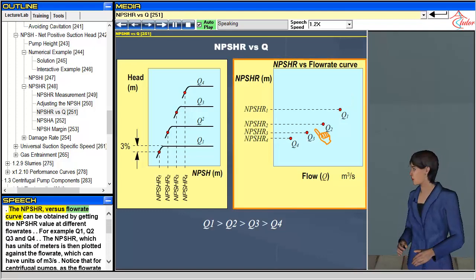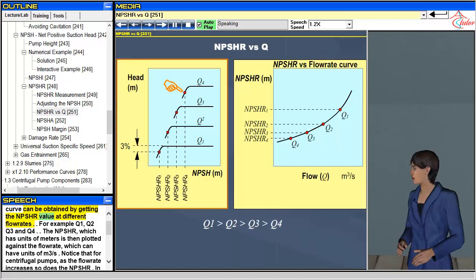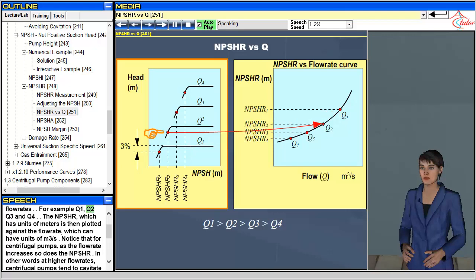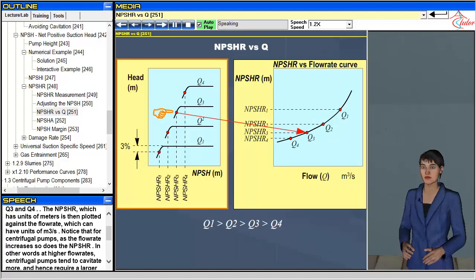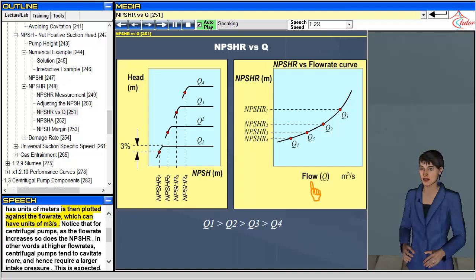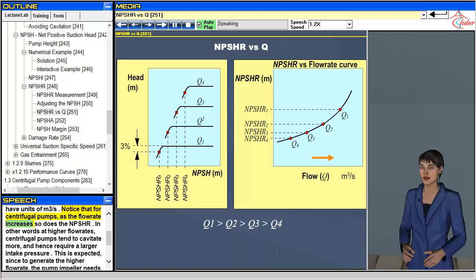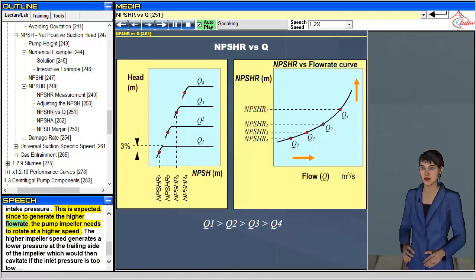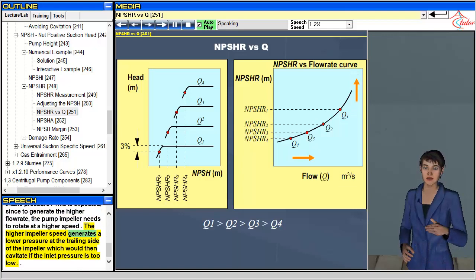The NPSHR versus flow rate curve can be obtained by measuring the NPSHR value at different flow rates — for example Q1, Q2, Q3 — and plotting NPSHR in meters against flow rate in meters cubed per second. Notice that for centrifugal pumps, as the flow rate increases, so does the NPSHR. In other words, at higher flow rates centrifugal pumps tend to cavitate more and hence require a larger intake pressure, because the pump impeller needs to rotate at a higher speed, generating a lower pressure at the trailing side of the impeller.